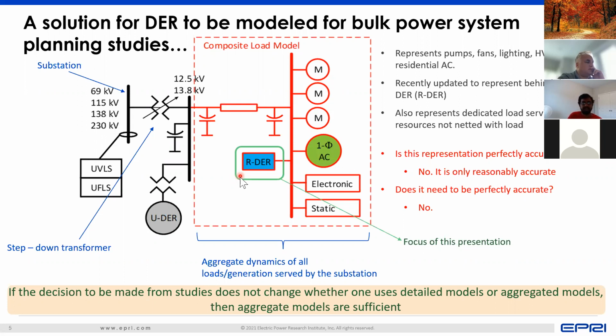The reason is that if we have to represent this feeder in detail, and I'll show you on the next slide what a big feeder looks like, it can take us a long time to get one simulation done. But instead, we use this aggregated model and the inference we obtain from it. Let's say we understand with this aggregated model that when you have a transmission system event, maybe 30% of the DER will trip. And let's say when we use a detailed model, instead of saying that 30% of the DER will trip, it says that only 25% or 35% will trip.